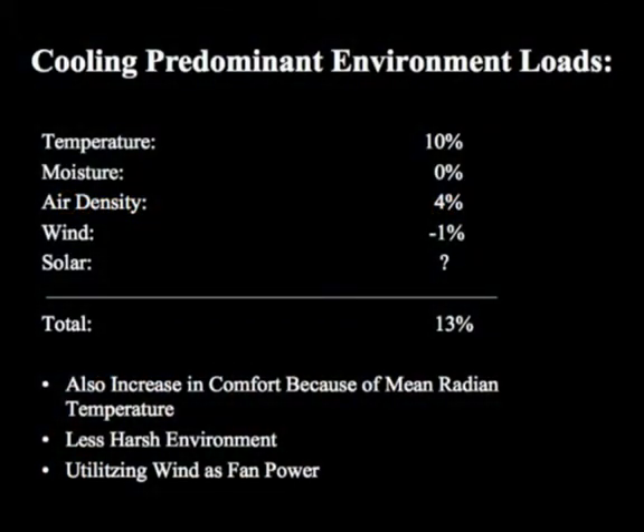For moisture, we didn't take any benefit, because in Dubai summertime is about 46 degrees with 30% relative humidity—it's too hot to get much moisture out of the air. But in other, lower-temperature locations, you can benefit during the transition season. Air density gives us about 4%. Wind actually increases the conduction heat gain as wind temperature picks up, so we have to subtract 1%. So for a 1-kilometer tower, just on the loads alone—forget elevators and other elements for a second—that could be a 13% reduction potential.